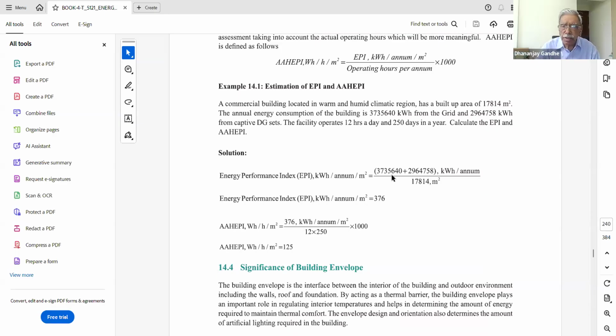Obviously, the energy performance index, if you calculate, would be total consumption: 37 lakh 35,640 plus 29 lakh 64,758. You can see this expression on the screen, divided by area 17,814. The answer you get is 376. So the energy performance index is 376 kilowatt hours per m square.